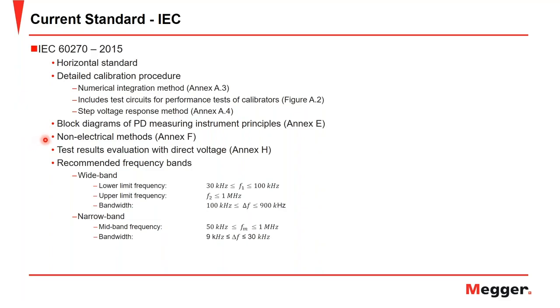Annex F has non-electrical methods. Annex H covers some test results with evaluation with direct voltage. And then the IEC 60270 has recommended frequency bands. This is what we were talking about earlier, when all the electrical methods use a bandpass filter to choose their frequency bands. The wideband has a lower frequency limit between 30 kilohertz and 100 kilohertz, while the upper frequency limit is less than or equal to 1 megahertz, with a total bandwidth between 100 kilohertz and 900 kilohertz. The narrowband frequency range has a midband frequency between 50 kilohertz and 1 megahertz, with a full bandwidth between 9 kilohertz and 30 kilohertz.